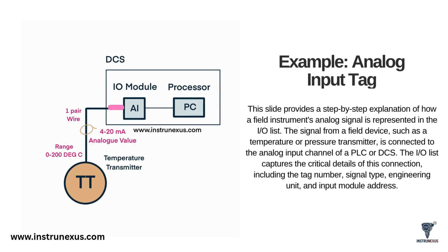Let's zoom in on a single tag type, the analog input (AI). A signal from a device like a temperature transmitter or a pressure transmitter is sent over a pair of wires to the analog input channel of the PLC or DCS. This signal is a continuous value, most commonly a 4 to 20 milliamp current, which represents the full range of the instrument's measurement. The IO List's job is to capture every critical detail about this one connection: the unique tag number, the signal type (4-20 milliamps), the engineering range (for example 0 to 200 degrees Celsius), and the exact input module address this wire pair connects to. Getting any of these details wrong will result in incorrect readings in the control system.